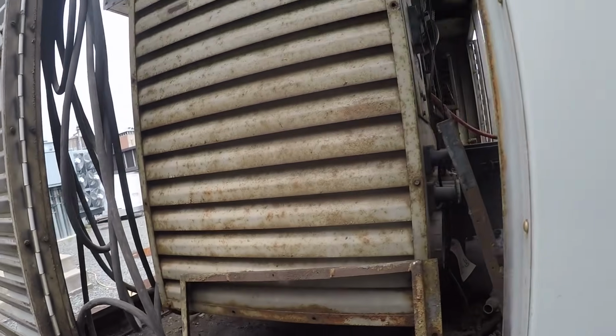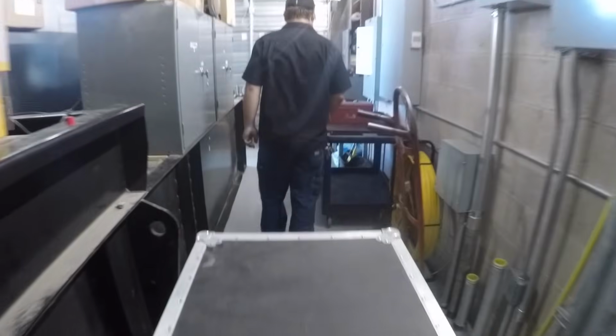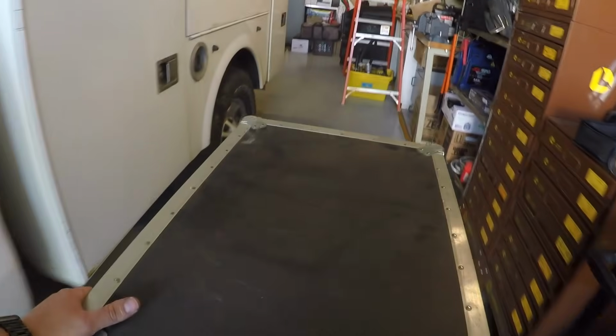It's been so long now that we can't really remember what exactly was happening, if it was not resetting, if there was a phase that was out, or if it would trip with any load on it. So we're going to go ahead and get the load banks out and load bank this sucker. We'll start out with one load bank, which is about 100 kW, see if it holds that, and then we'll bring out two. This is a 230 kW generator, so we'll put 200 on it for at least an hour and see if she holds.